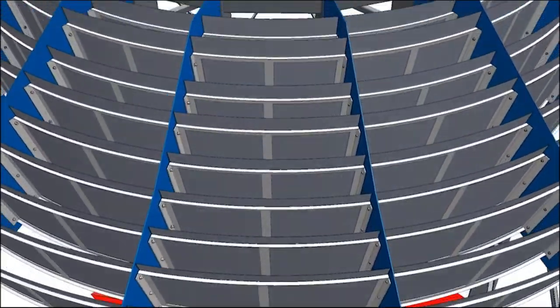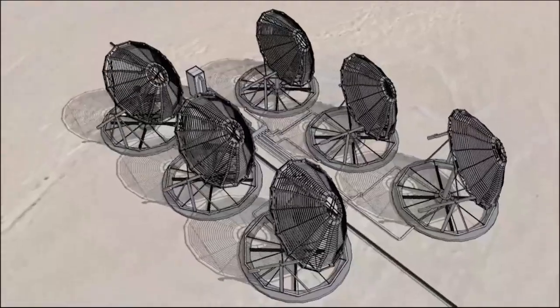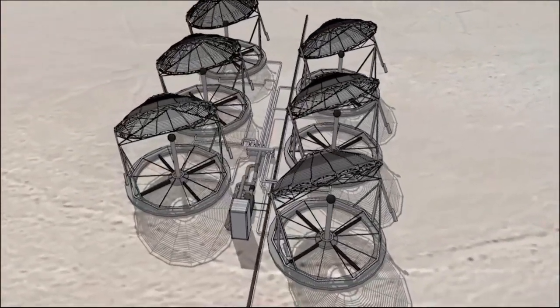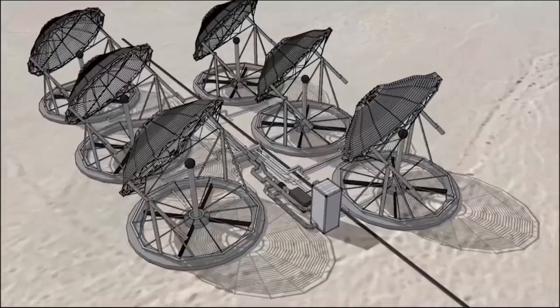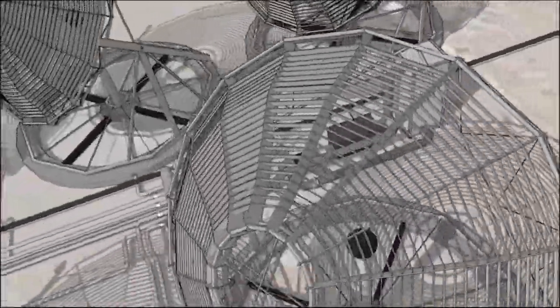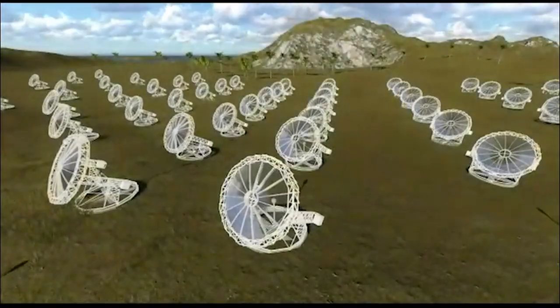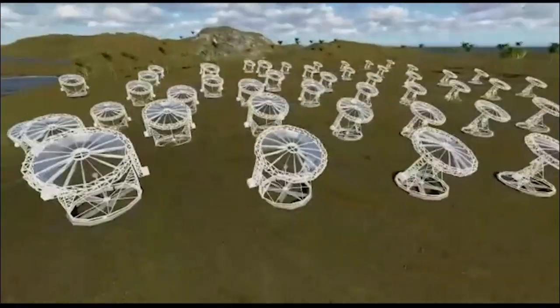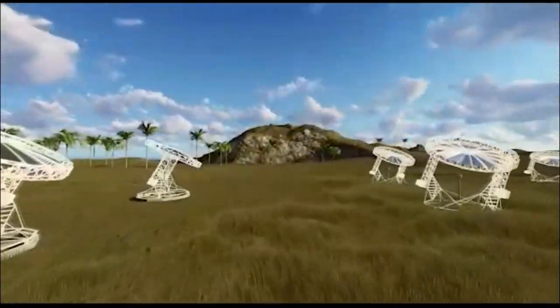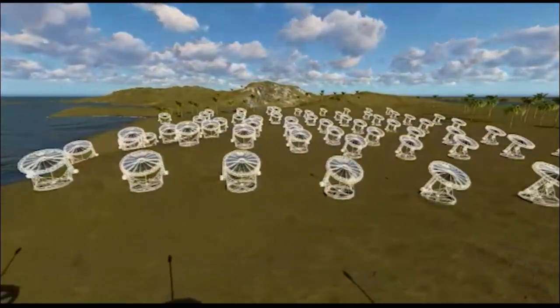The receiver is shielded by an innovative hood to reduce waste heat through convection and radiation. A cluster of six units is designed and simulated for shadowing, taking up an area of only 2,000 square meters to produce around one megawatt thermal during daytime, or half a megawatt for 12 hours of operation overnight. The area needed for ASC is about one-third of the area needed for any other solar system to produce the same energy. A full power plant using the ASC does not require totally flat land; only the area under each ASC needs to be flat, and each unit can be placed at a totally different elevation with a land gradient of more than 10 percent.